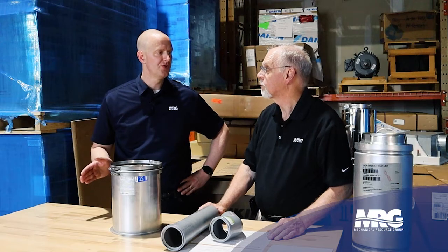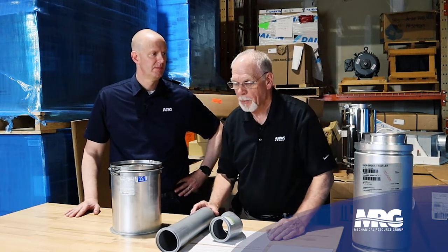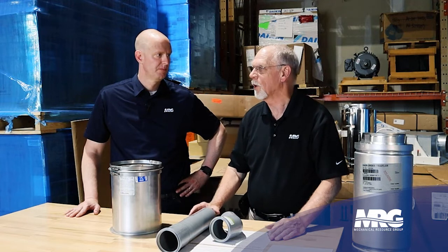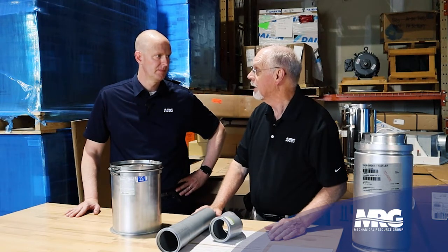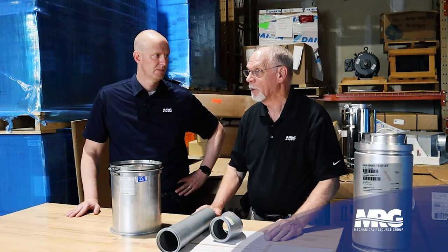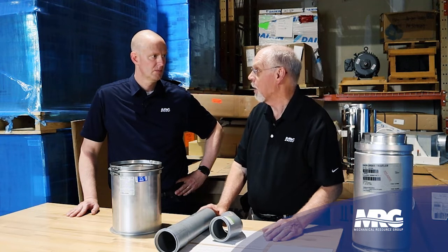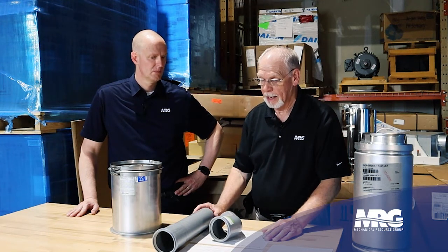When would you go double wall or single wall for a vent pipe? We use our single wall pipe when you are in an area where you don't have the possibility of people being around it to be burned. You can put that in the ceiling space if you wanted to, and if it was exposed. I wouldn't put it where it was concealed, but I would put it where it was exposed. Mainly it's just for safety, so that people don't get around it and get burned on the thing. And that's for all of it.